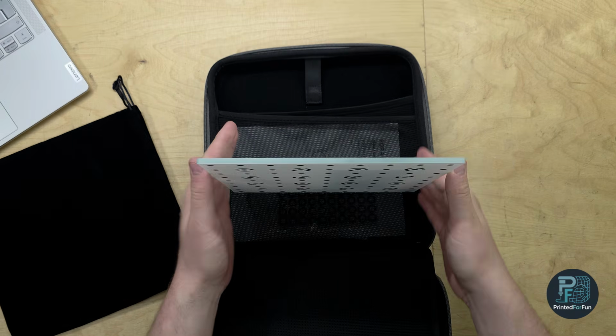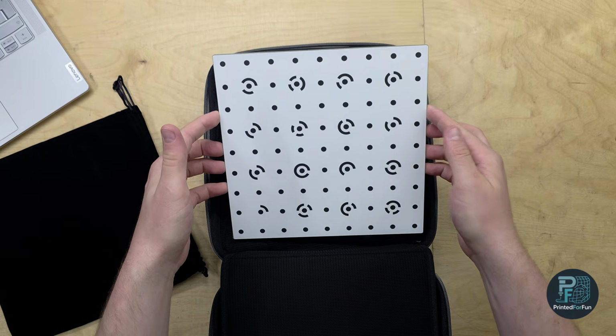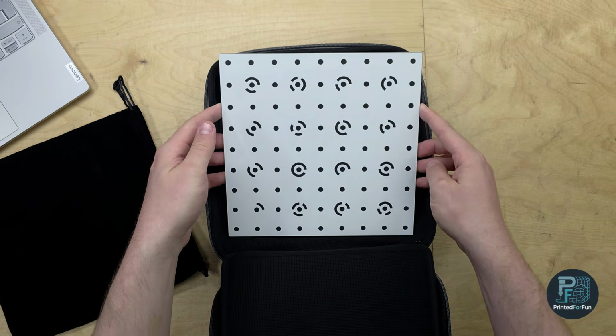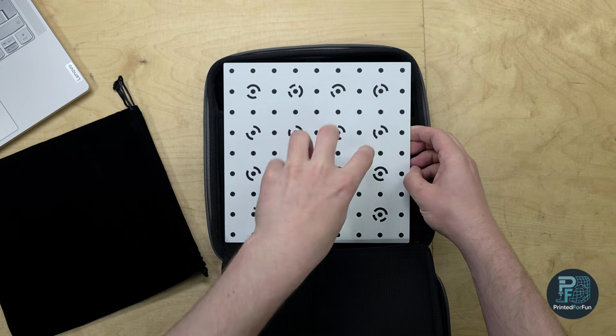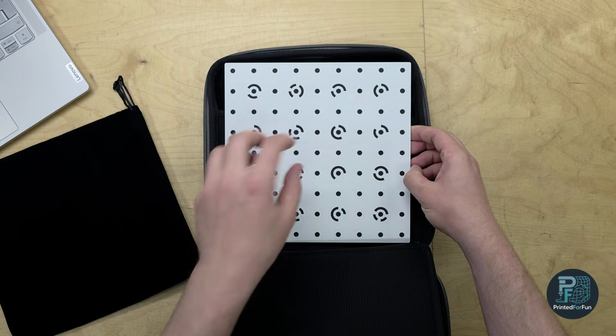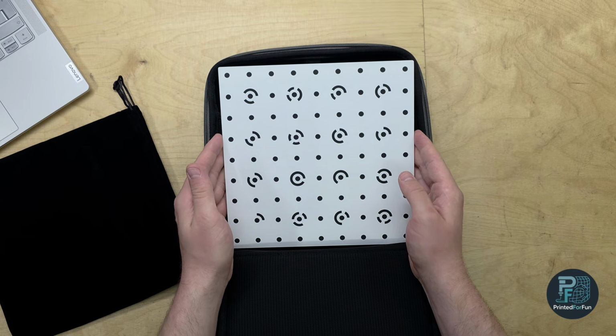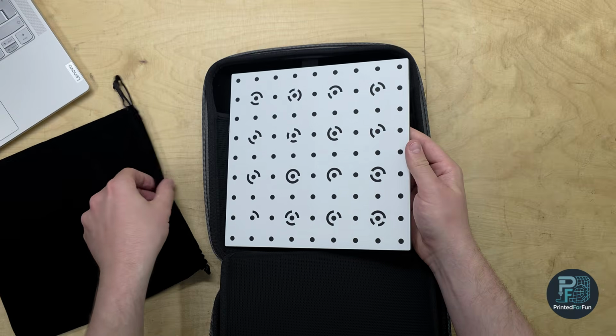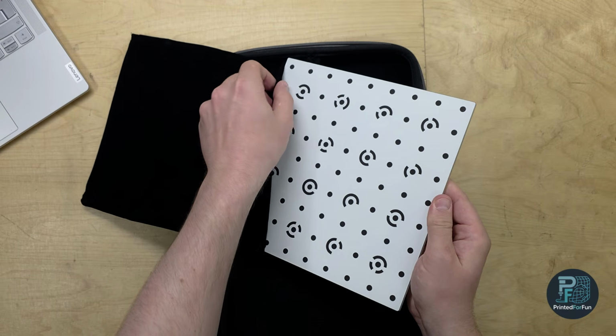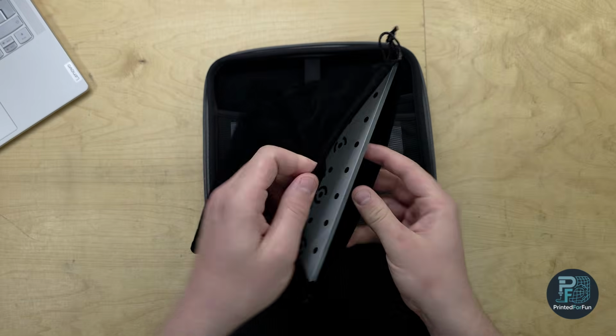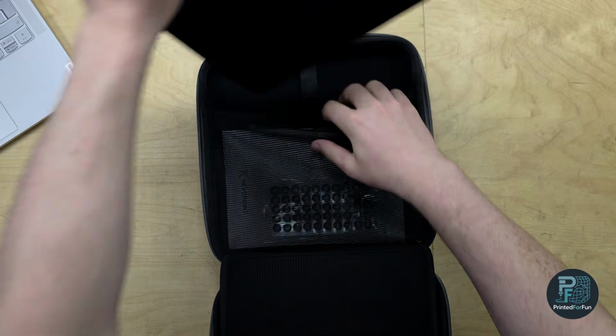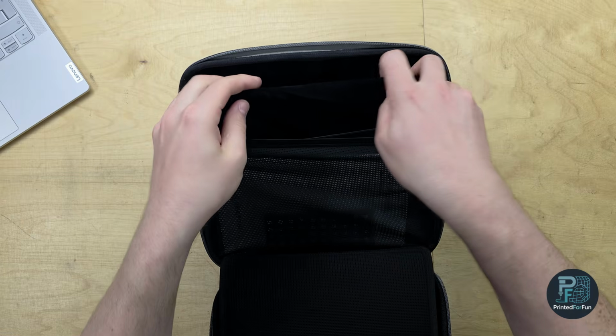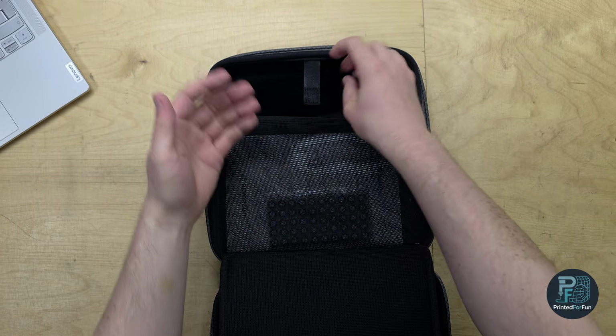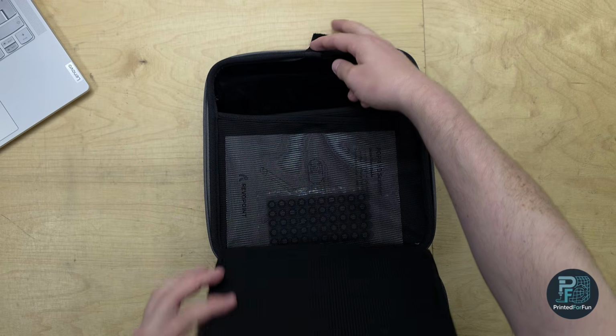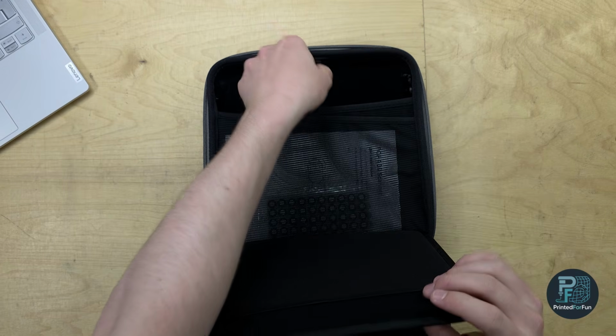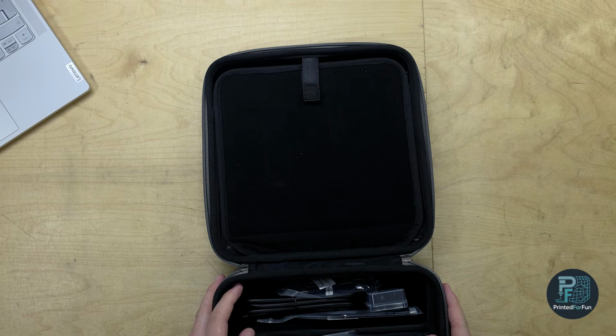What's also important, if you handle these boards, just grip them on the side, because you don't want to get smudges on the front face, or even worse, scrape some of these marker dots and coded targets, because this could decrease your calibration results. But best is to just store it in the included bag most of the time, unless you are calibrating it. And this bag is also a good ground for calibration. So when you calibrate it, take it out of the bag and place it on the bag so it doesn't get scratched.